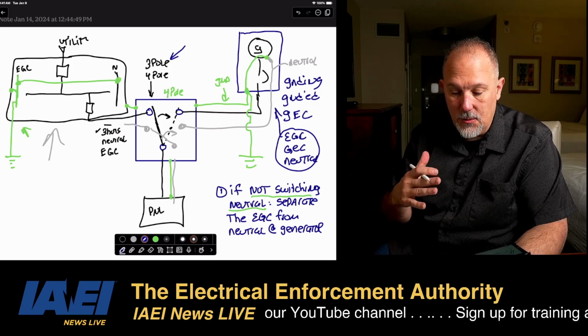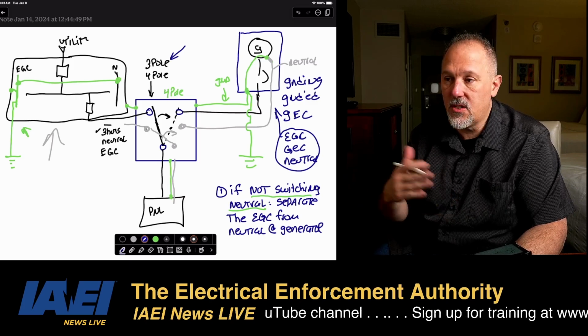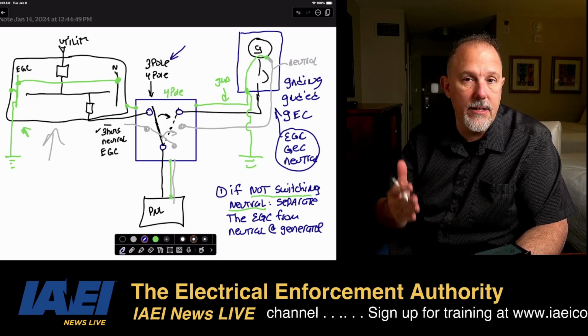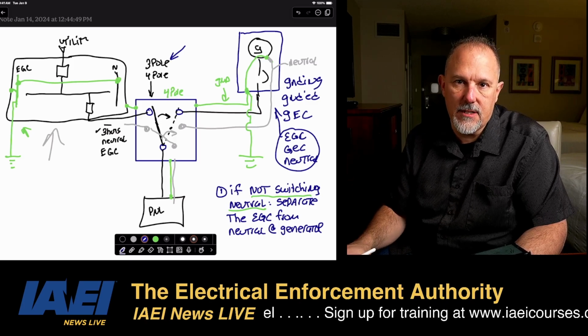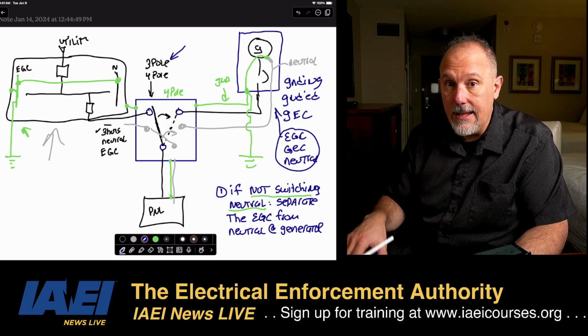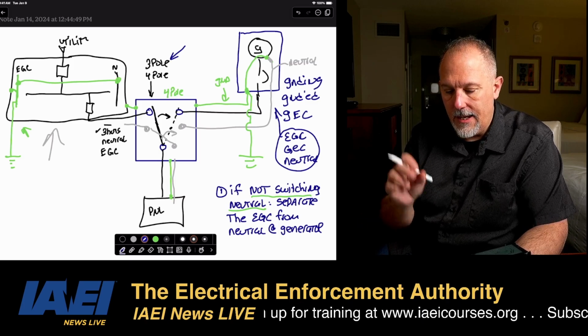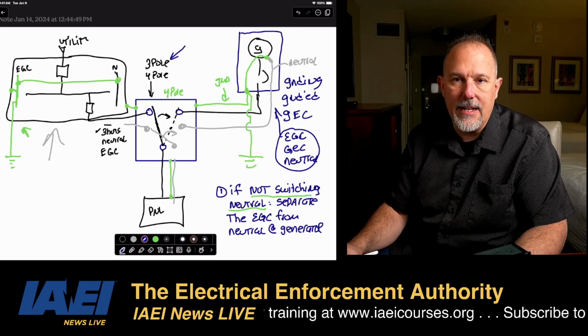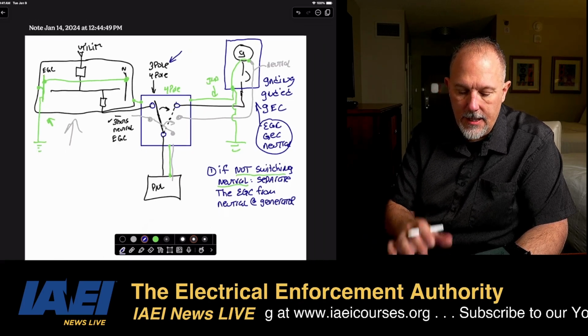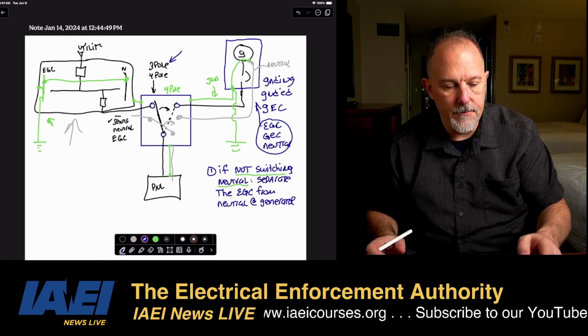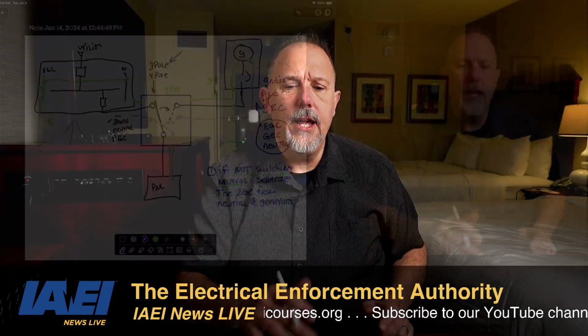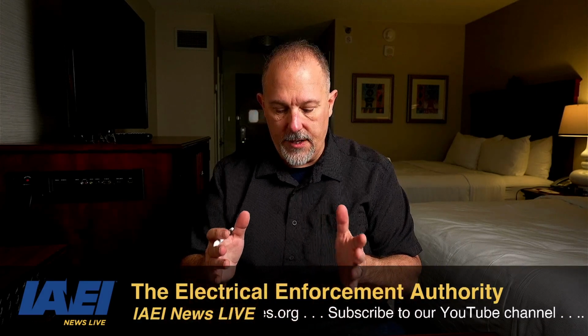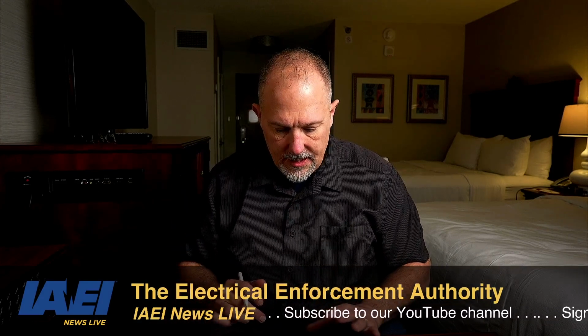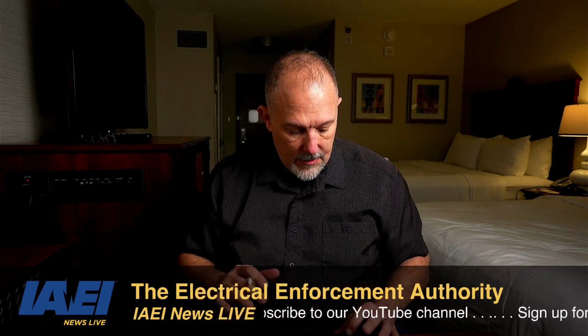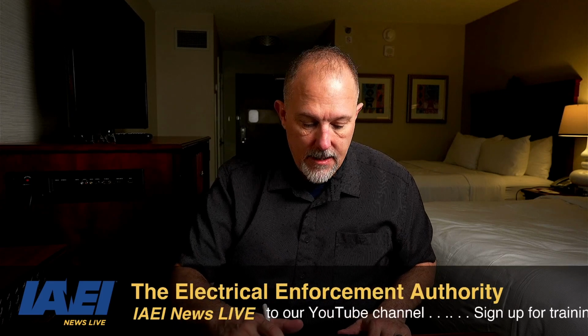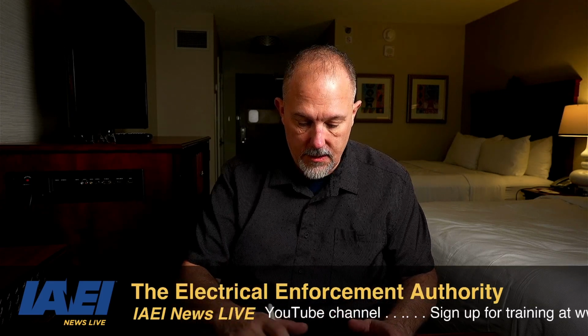And all we had to do was basically say, do I have a 4-pole or a 3-pole? Am I switching the neutral? Am I not switching the neutral? If I'm not switching the neutral, then it's a non-separately derived system. If I'm switching the neutral, then it is a separately derived system, and I need to be bonded and grounded in that generator. Make sense? So that's why it's really important to understand separately derived systems and non-separately derived systems, and make sure that you have the grounding and the bonding all being performed in the right locations.